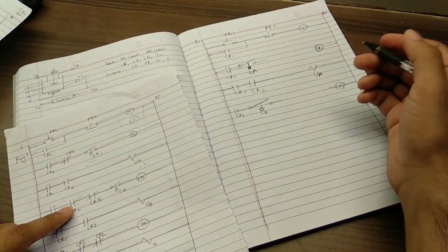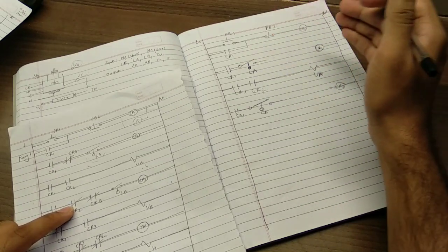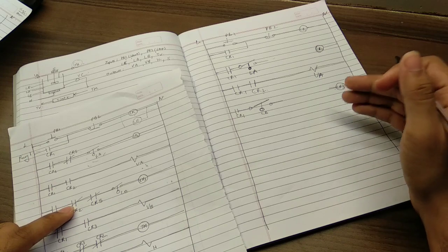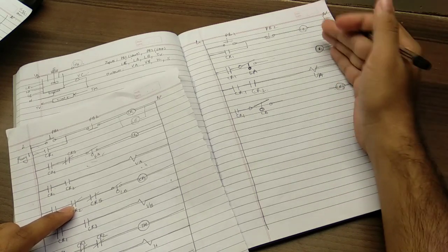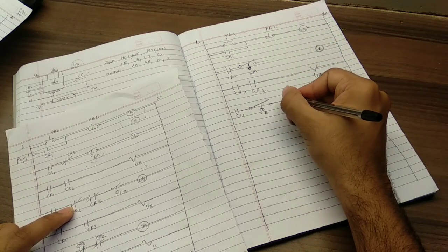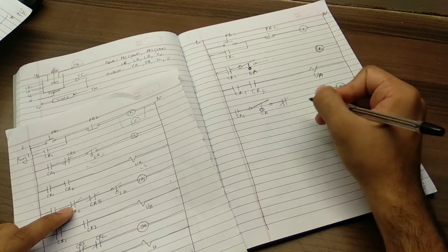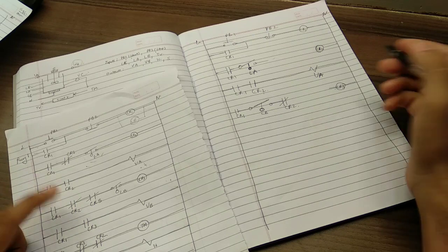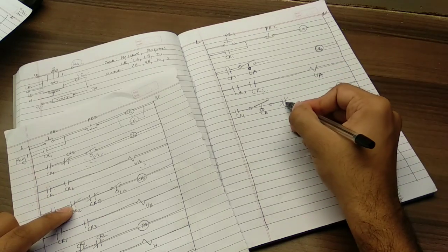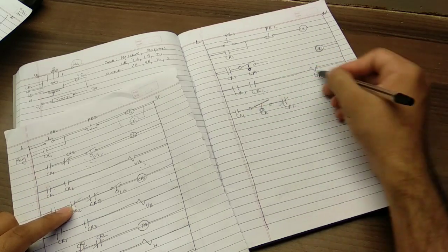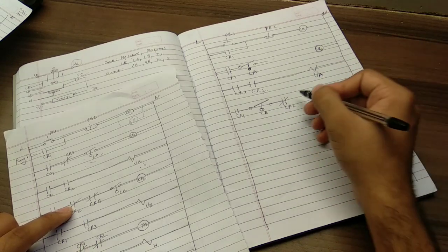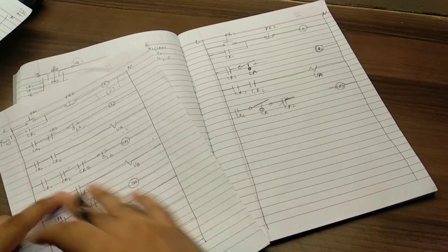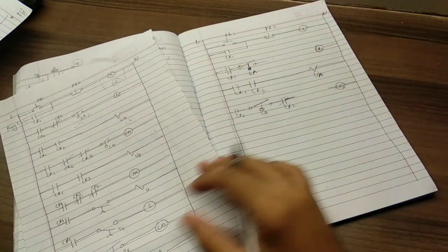So then we have to state a condition: when LA or valve A is actuated, we do not want valve B to be actuated. So for valve B to be not actuated when valve A is actuated, we'll just add a not relay. So not when CR2. That means when CR2 is on, this would be off, so that when valve A is on, this rung would be off. We'll just keep space for future CR5 or whatever that will come in.